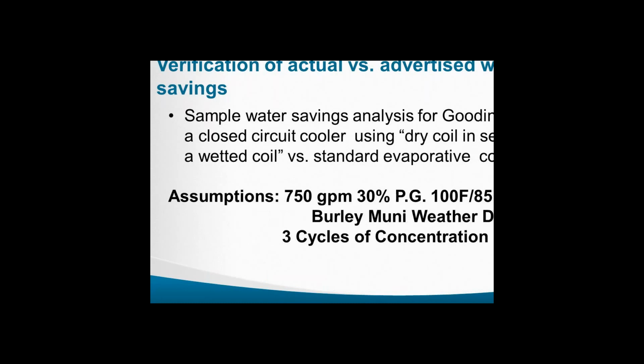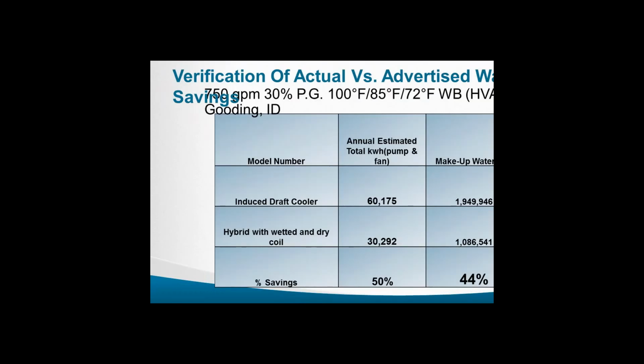Used 3 cycles of concentration. I don't know what the water quality is like down there, but hopefully you can get 3. And I selected a commercial HVAC load profile and ran these conditions, comparing a basic induced draft closed circuit cooler versus a hybrid. You can see the realized energy savings: 50% energy savings, 44% water savings. So it does give you some significant water savings.